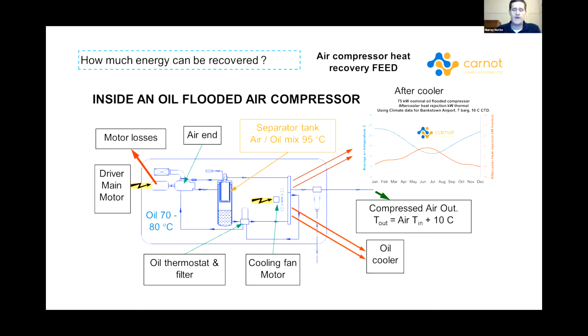Now you've heard people talk about, Selwyn was talking about 80 kilowatts, 80% of the heat going to the oil cooler. It is variable. It depends upon how the compressor is operating. And as you can see in that graph, the temperature being lost and the energy lost through your aftercooler varies with the temperature of the day and the humidity of the air coming into the machine. So if you've got wet, humid air coming into the machine, you've got to condense a lot of water, you've got to reject a lot of heat in your aftercooler. So the actual heat loads vary with the time of the day, with the season, and with how heavily loaded your air compressor is.